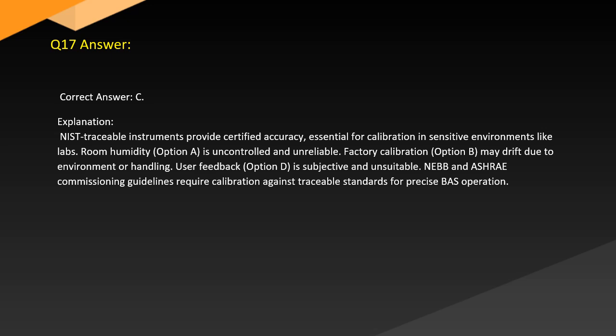Answer. Correct answer: C. Explanation. NIST traceable instruments provide certified accuracy essential for calibration in sensitive environments like labs. Room humidity, option A, is uncontrolled and unreliable. Factory calibration, option B, may drift due to environment or handling. User feedback, option D, is subjective and unsuitable. NEBB and ASHRAE commissioning guidelines require calibration against traceable standards for precise operation.